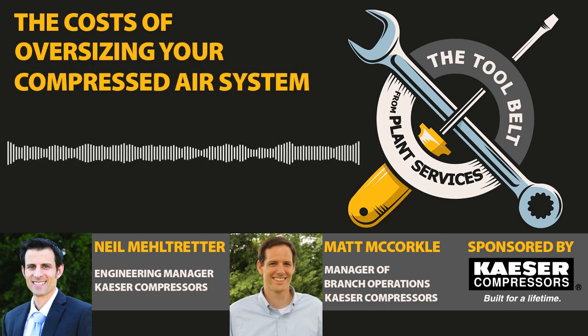They're seeing that the issue is that compressors are really inefficient at partial load. Compressors are efficient when they're fully loaded or when they're off. It really doesn't matter what the control method is. That's generally how it is. And so it ends up there's a lot of waste.